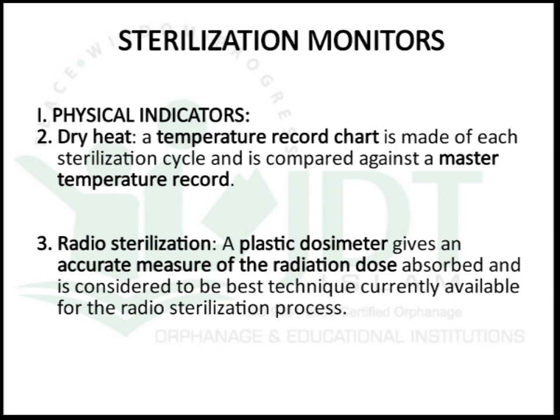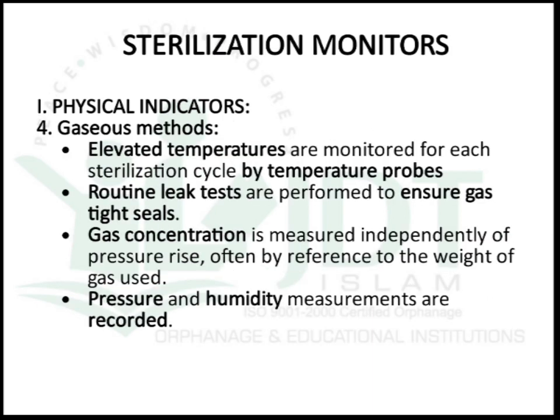For physical indicators in radiation sterilization, a plastic dosimeter is used, which gives an accurate measure of radiation dose absorbed. This is considered the best technique currently available for the radiation sterilization process.